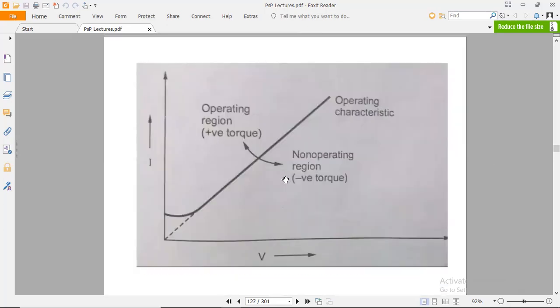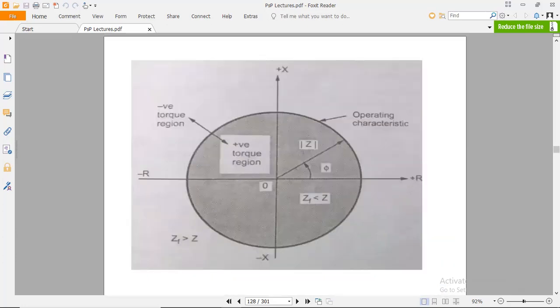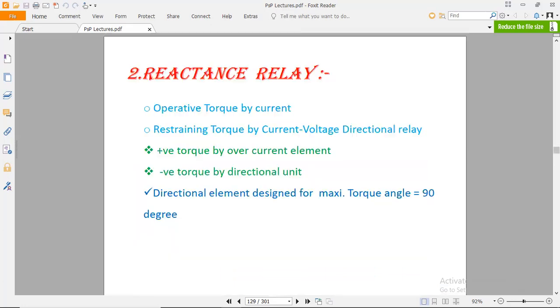Operating region: positive torque. Non-operating region: negative torque. This is the operating characteristic, the difference between current and voltage. Further, the concept of the impedance relay can also be understood through a scenario, but we are discussing the theoretical concept. Number two, the reactance relay: operative torque by current, which is an important aspect of the reactance relay. Mostly, the types of distance relay are defined as the impedance relay and the reactance relay.